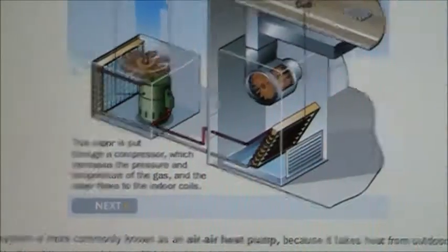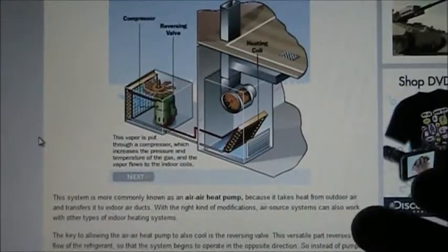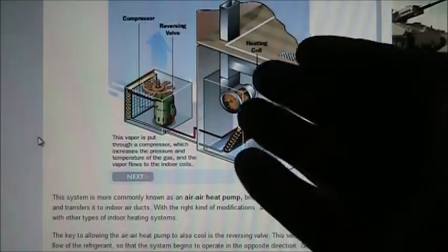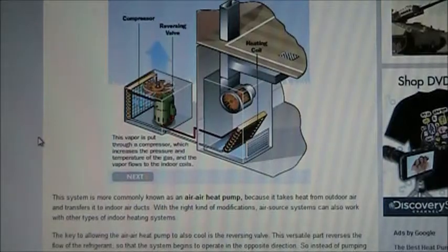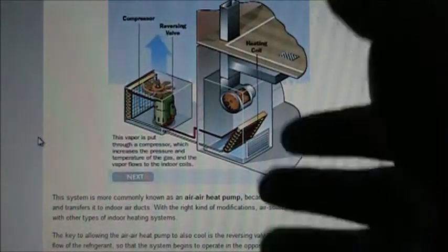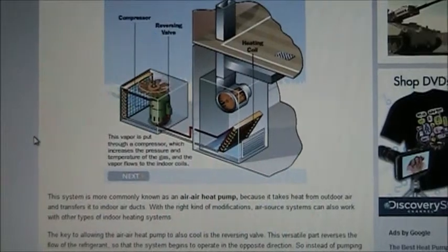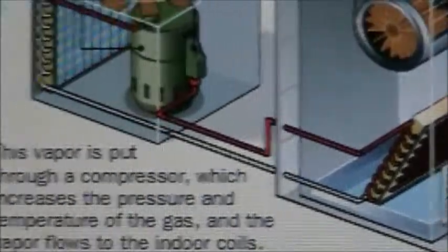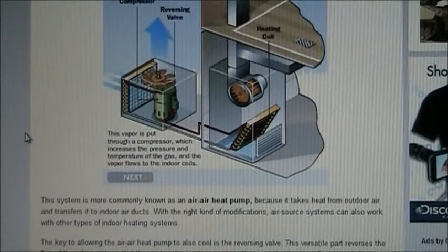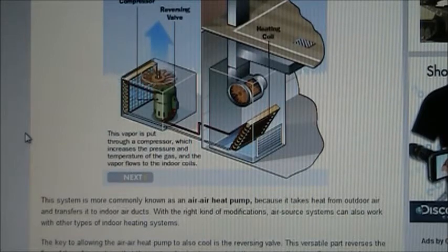Now, like I said a minute ago, sometimes heat pumps don't work that efficiently in cold weather. That is why, if it's known to get real cold where heat pumps are, typically in the air handler there'll be backup electric heat strips. Some people have dual fuel systems, which combines a heat pump and a gas furnace. The heat pump is more efficient when it's in the 30s, 40s, 50s out, and down below 20 the gas furnace is then more efficient. But as you can see there now, that has become the condenser coil, and now that is the evaporator coil when a heat pump runs in heat mode. That's why a reversing valve is called a reversing valve, because it is a valve that completely reverses the flow of the refrigerant and reverses what the system's doing.